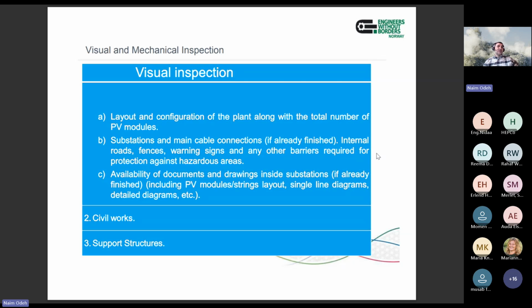For the documentation, we mean the documents that you have with you while doing the inspection, which is the drawings and so on. The other type of drawings should be saved at site itself, usually inside electrical rooms, and it is mandatory to have a copy of the relevant SLDs. This is important for future operation, and also in case of emergency, the external team who comes to take necessary action needs to see the actual drawings to be able to deal with this equipment.